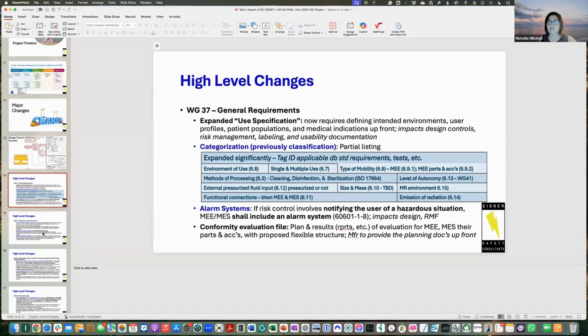So now with the fourth edition coming out, and for the class 2A, particularly ours, we're working on MDR, but it doesn't have to be until December 2028. And as time goes on, do you think they will change the requirements? Say, okay, if you want to be certified under MDR, then you will have to have 4th edition for your 60601-1 as well. Would that happen?